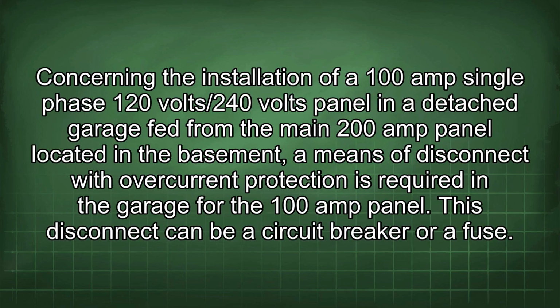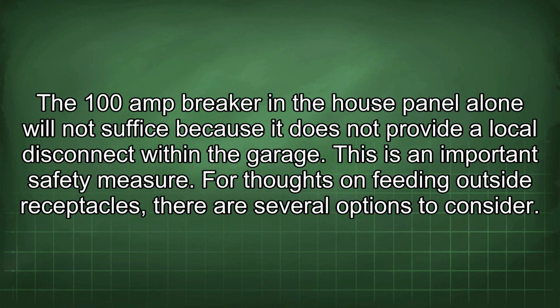Concerning the installation of a 100-amp single-phase 120-volt/240-volts panel in a detached garage fed from the main 200-amp panel located in the basement, a means of disconnect with overcurrent protection is required in the garage for the 100-amp panel. This disconnect can be a circuit breaker or a fuse. The 100-amp breaker in the house panel alone will not suffice because it does not provide a local disconnect within the garage. This is an important safety measure.